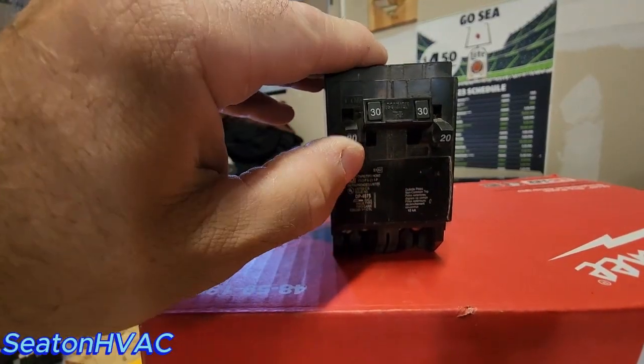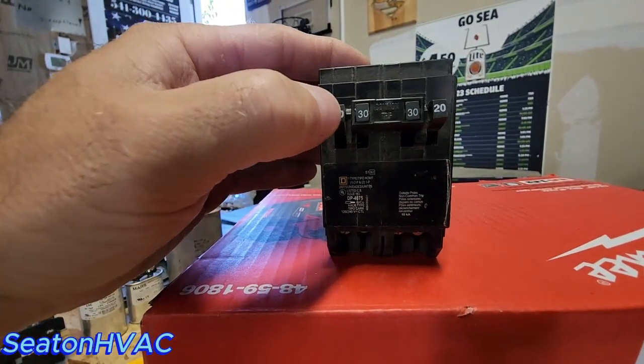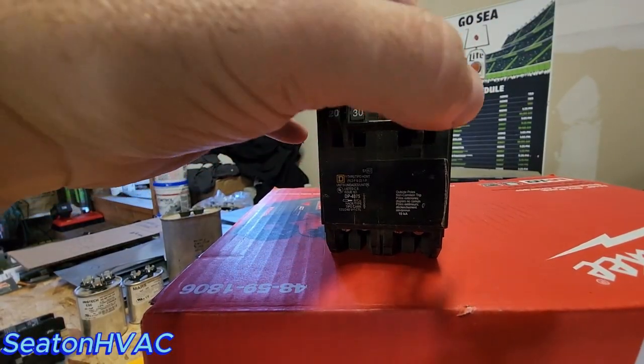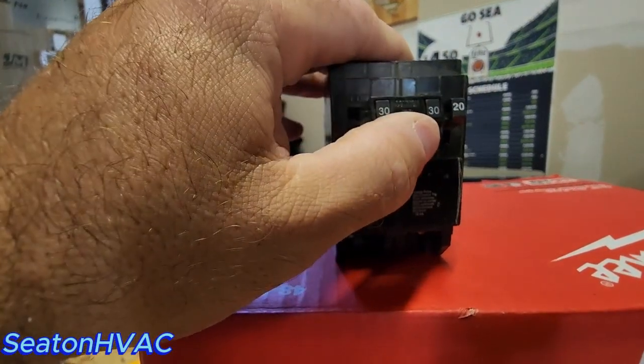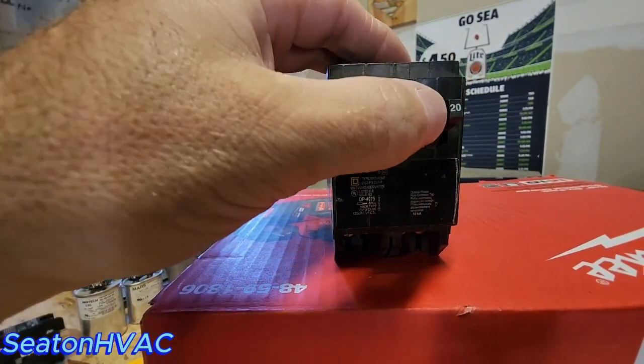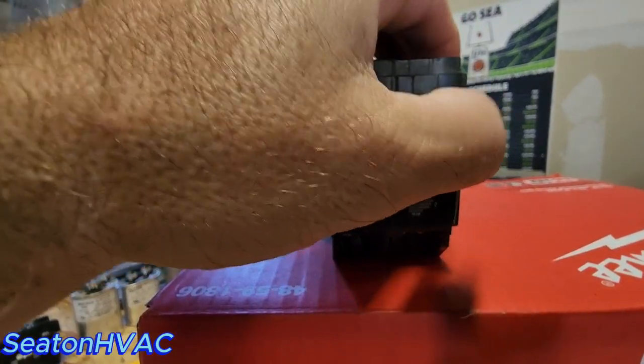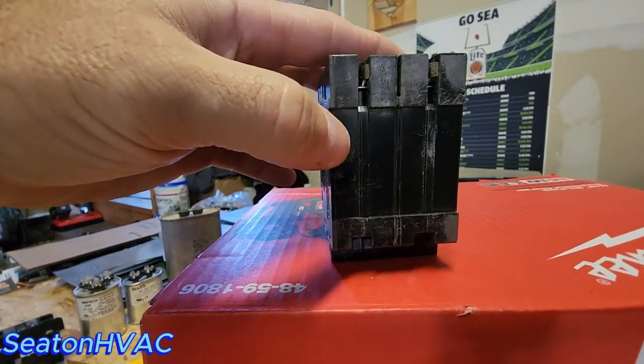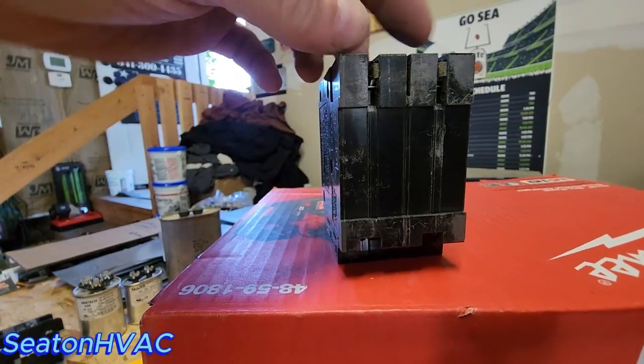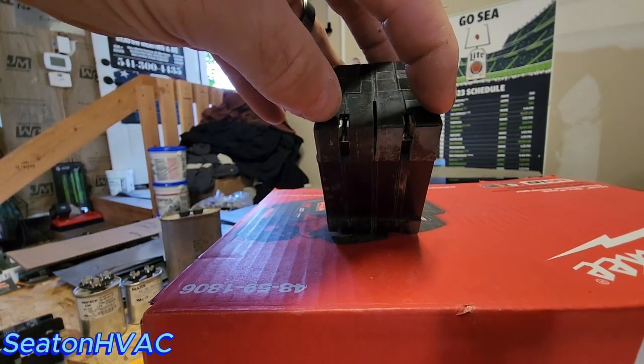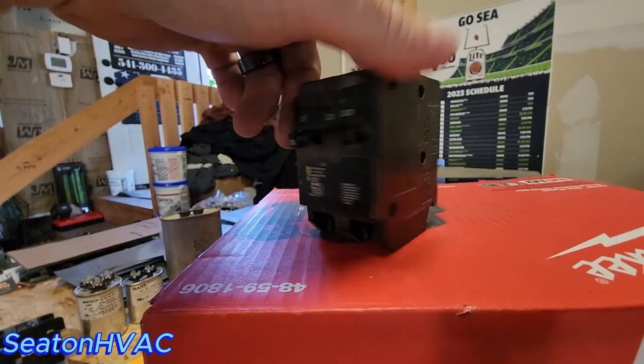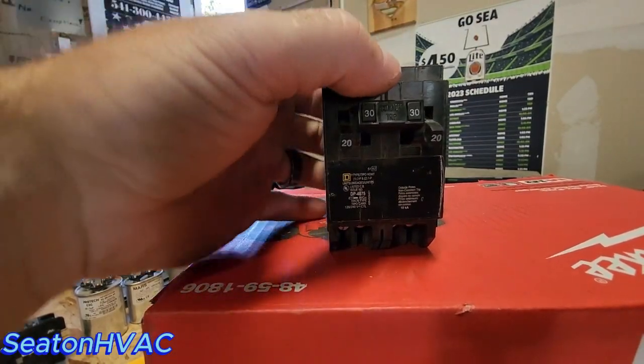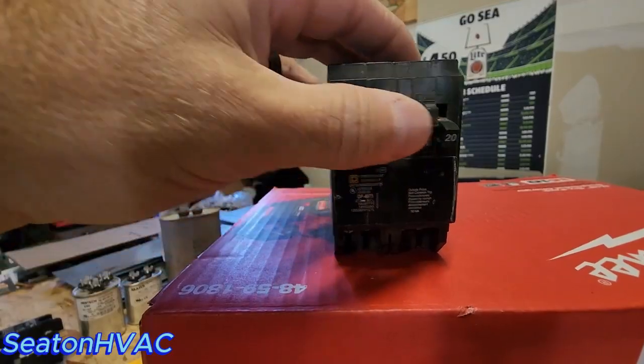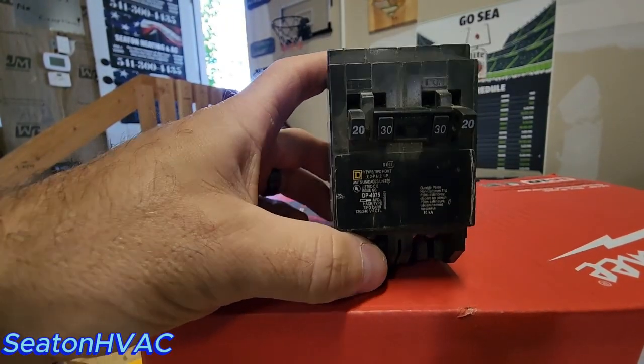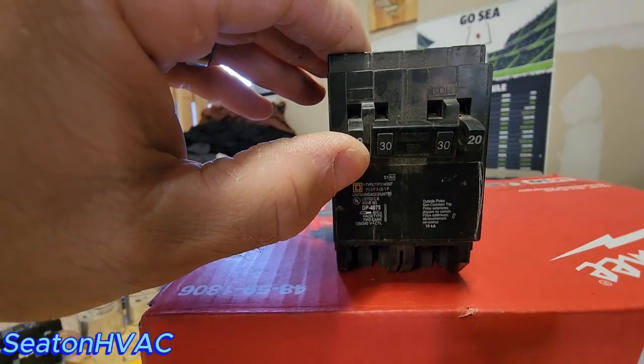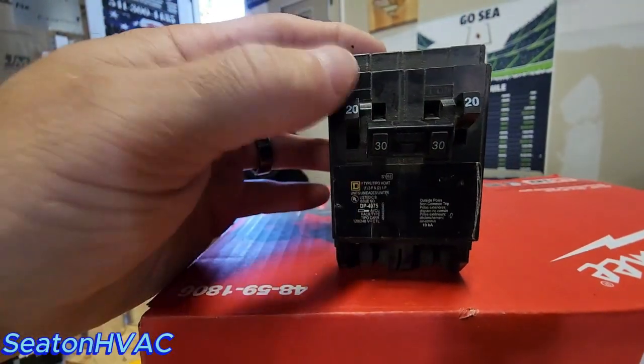So what you have here is a 120 volt circuit, 120 volt circuit, like lights and plugs, a garage, and then your heat pump or AC, or a range or whatever, which is 240 volts. So you've got 120 volts, 240, 120. I guess you can't see the teeth. It must all be done internally inside the breaker, but you still have 120, 120, and then 240 there. They just do it differently on these. But yeah, there's your quad breaker. If you needed to minimize and fit some stuff in and the panel didn't have room, this is a breaker they would use. So this will usually be labeled lights and plugs for something, and same with this, or like a microwave maybe.